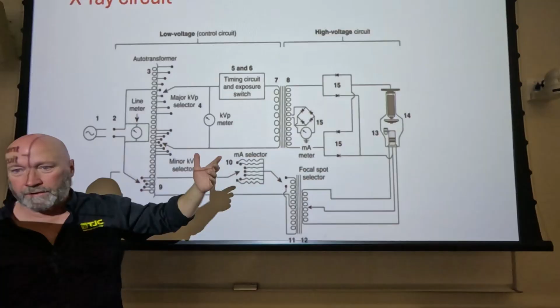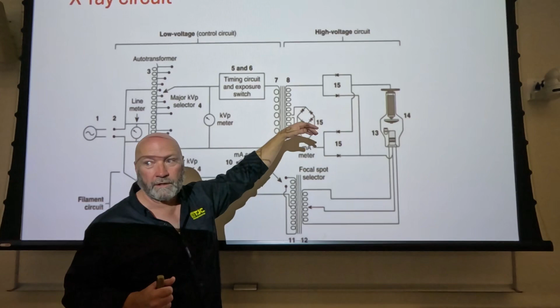We have to know how much we're actually getting through the circuit, right? So we have to put it on the secondary side, but it's wired into the center of the secondary side where voltage is always at 0. Don't ask me how that works. I don't know. I don't care. Just know that it works. That's all you need to know. So it's wired into the secondary side of the high voltage transformer. So it still works off of low voltage, even though it's on the secondary side of the high voltage transformer, right?